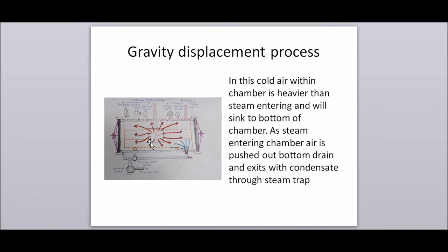Gravity displacement process: the cold air within the chamber is heavier than the steam entering and will sink to the bottom of the chamber. As steam enters, air is pushed out of the bottom drain and exits with the condensate through a steam trap.